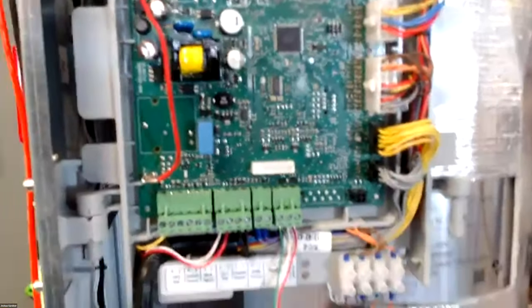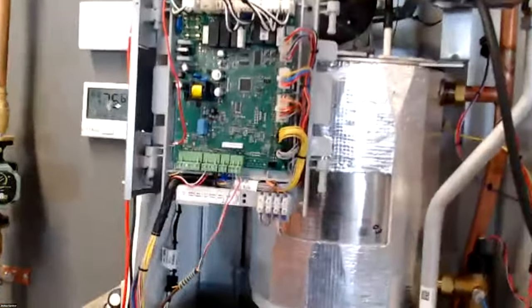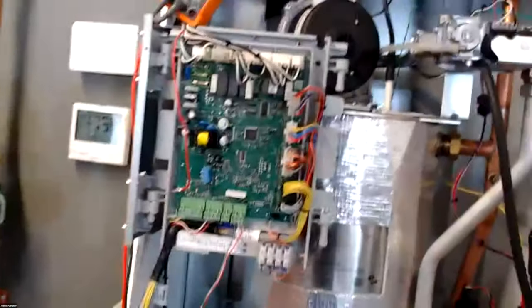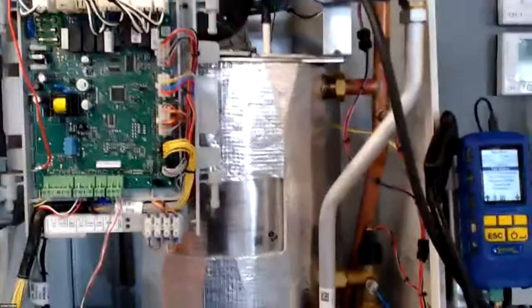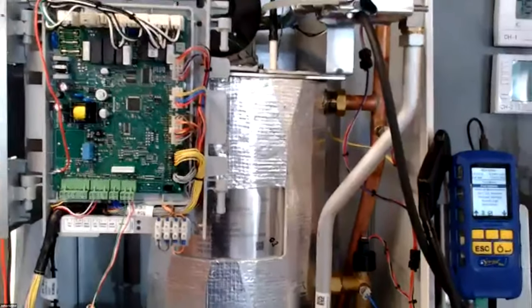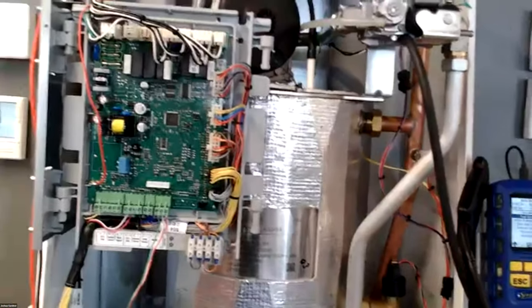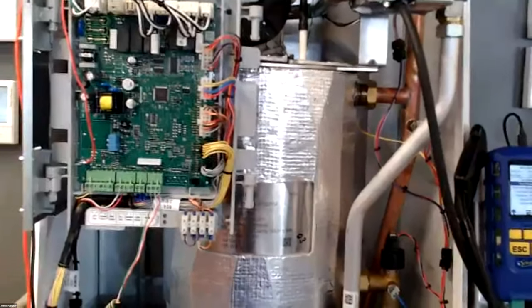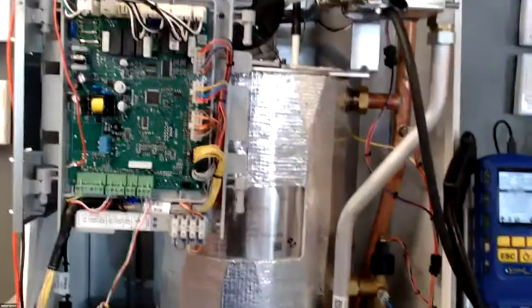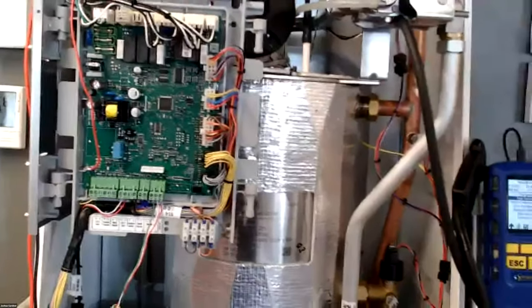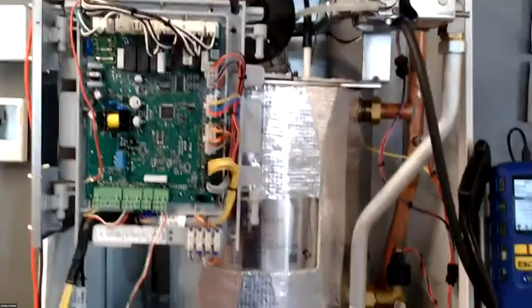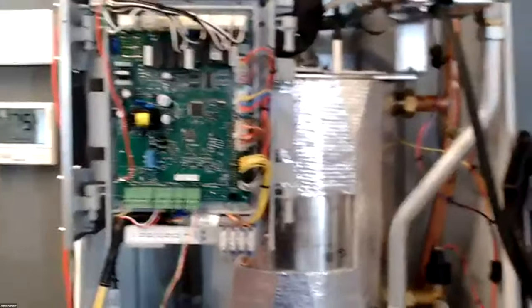On our flame signal, we'll drop out about 0.75 microamps. Low fire, if the burner's set up properly, you'll typically run around 3 to 5 on low fire. And then when you get up into high fire, you'll be up in the 20 to 28 range, is kind of what you're looking for. So if you're a little weaker on there, definitely look at your flame, your igniter, if there's some issue or something dirty with that, or also check your combustion.